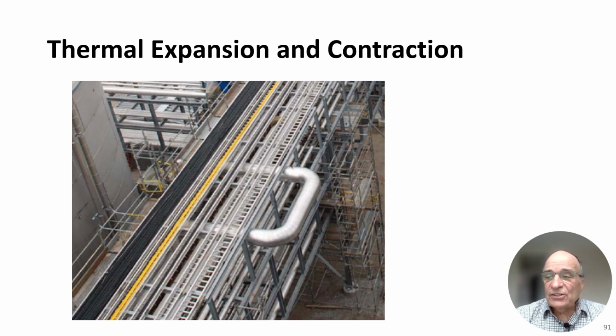Thermal expansion and contraction. Stainless steel contracts about 2.5 inches per 100 feet. And that's a rough number that I looked up, and 2.5 inches per 100 feet for a temperature change of about 320 degrees, which would be ambient temperature down to minus 260. So you have to take that into account using either a bellows or expansion joints. This is an expansion joint here. It allows the pipe to flex. So you'll see these in many locations along a run of piping. Or you could have expansion bellows that allow the bellows to contract and expand as needed to avoid overstressing the piping.